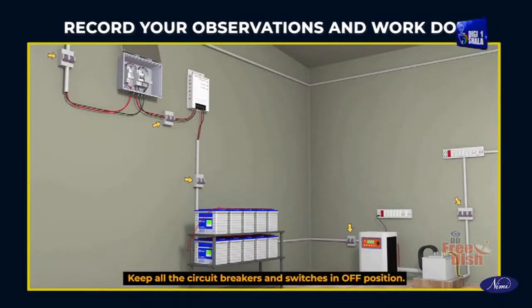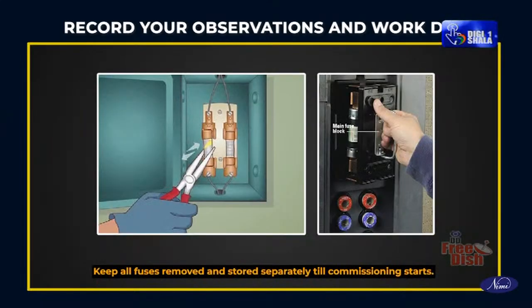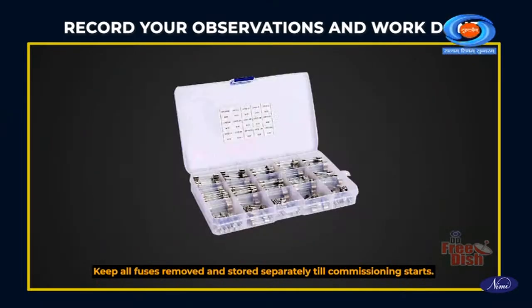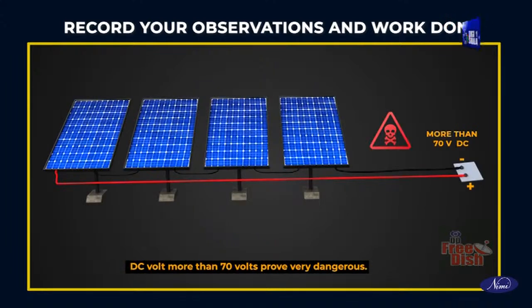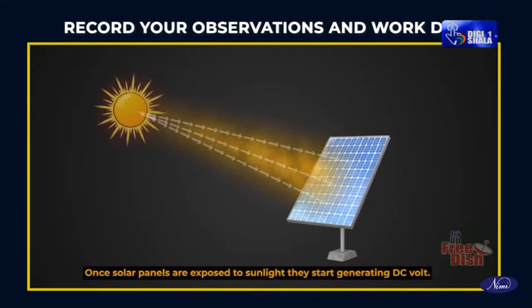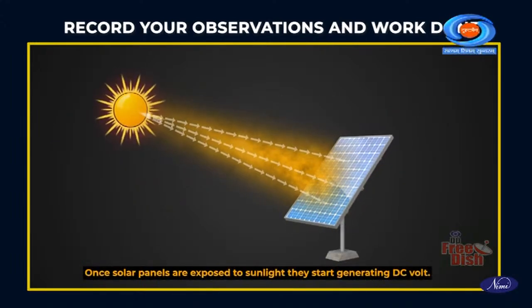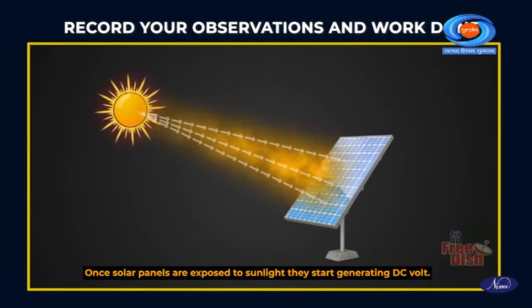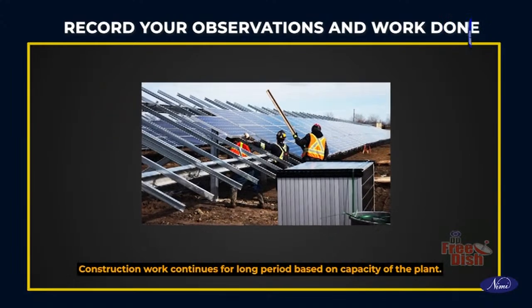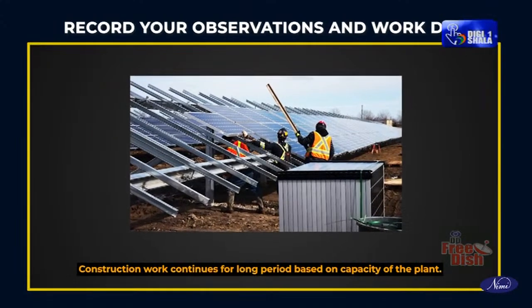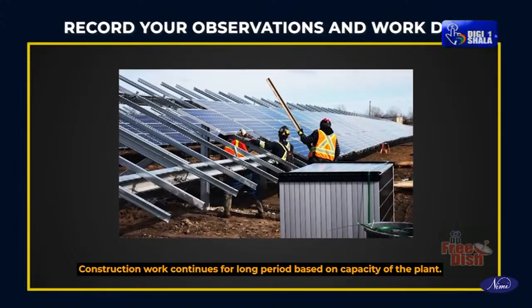Keep all the circuit breakers and switches in off position. Keep all fuses removed and stored separately till commissioning starts. DC voltage more than 70 volts proves very dangerous. Once solar panels are exposed to sunlight, they start generating DC voltage. Construction work continues for a long period based on capacity of the plant.